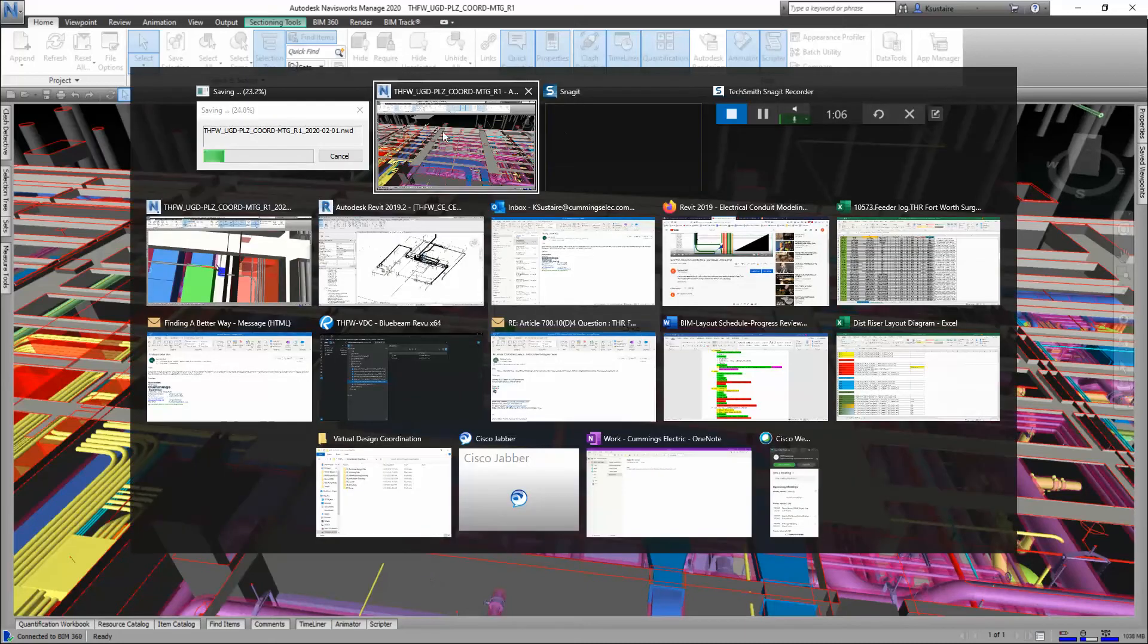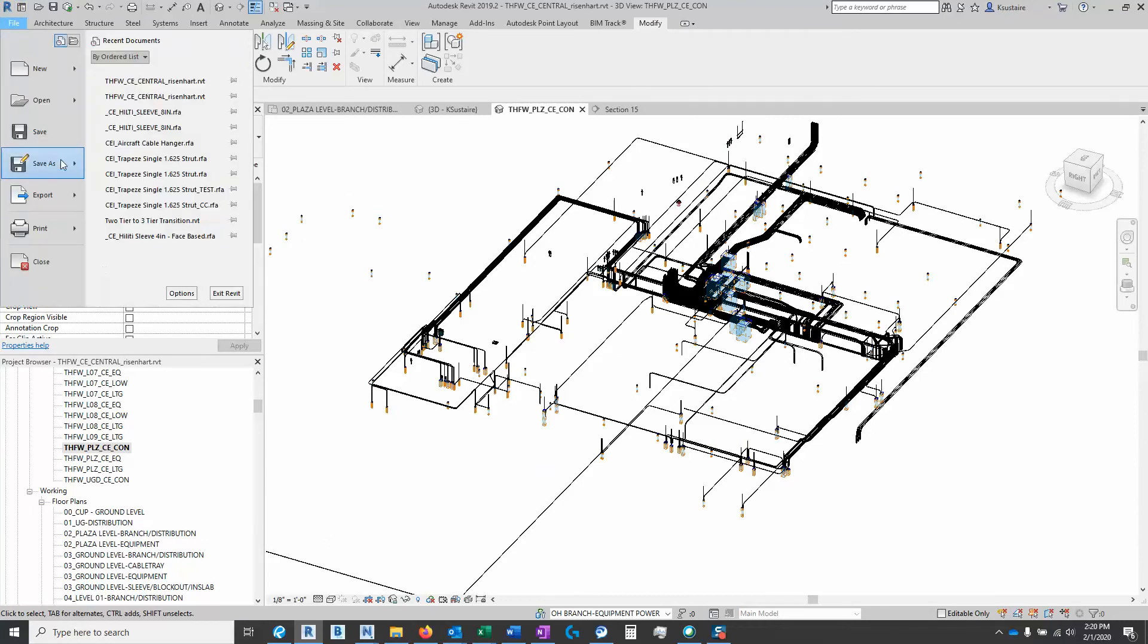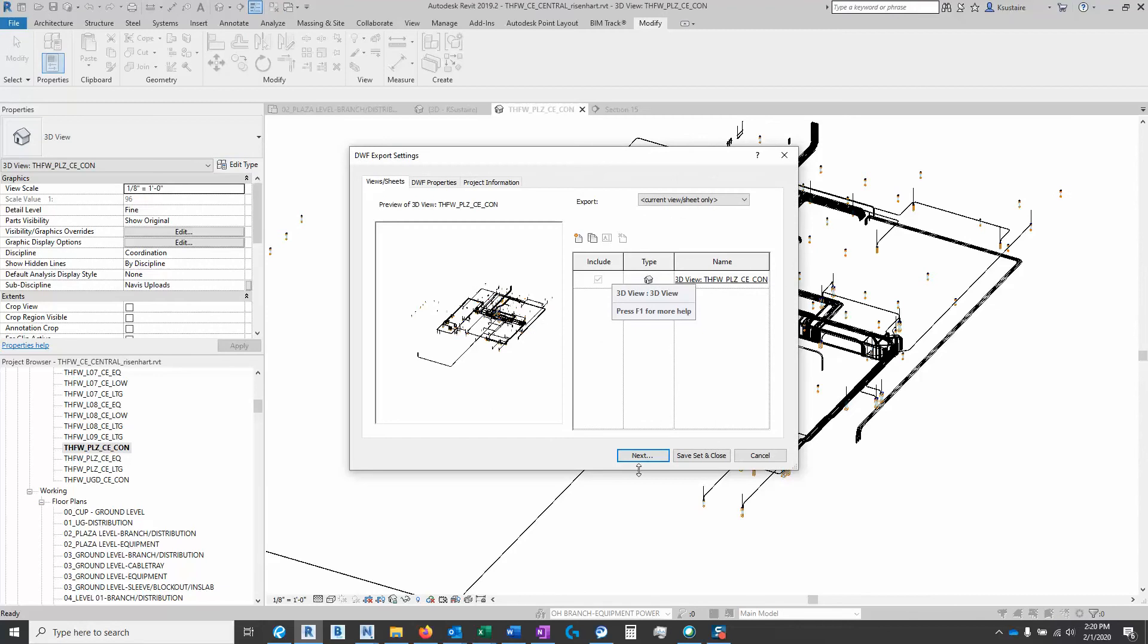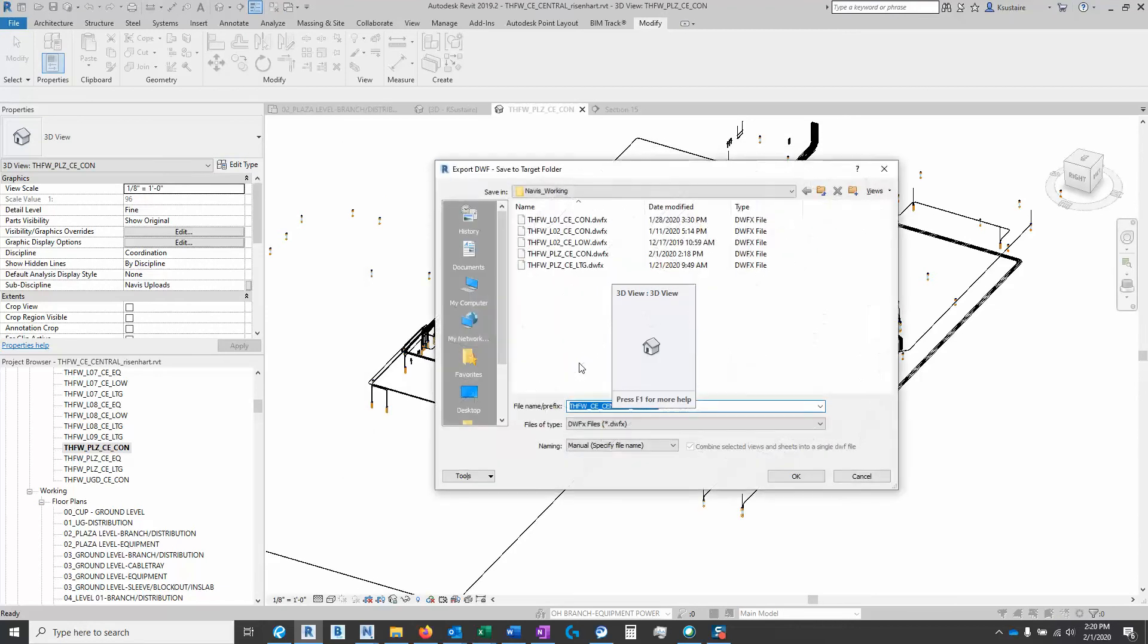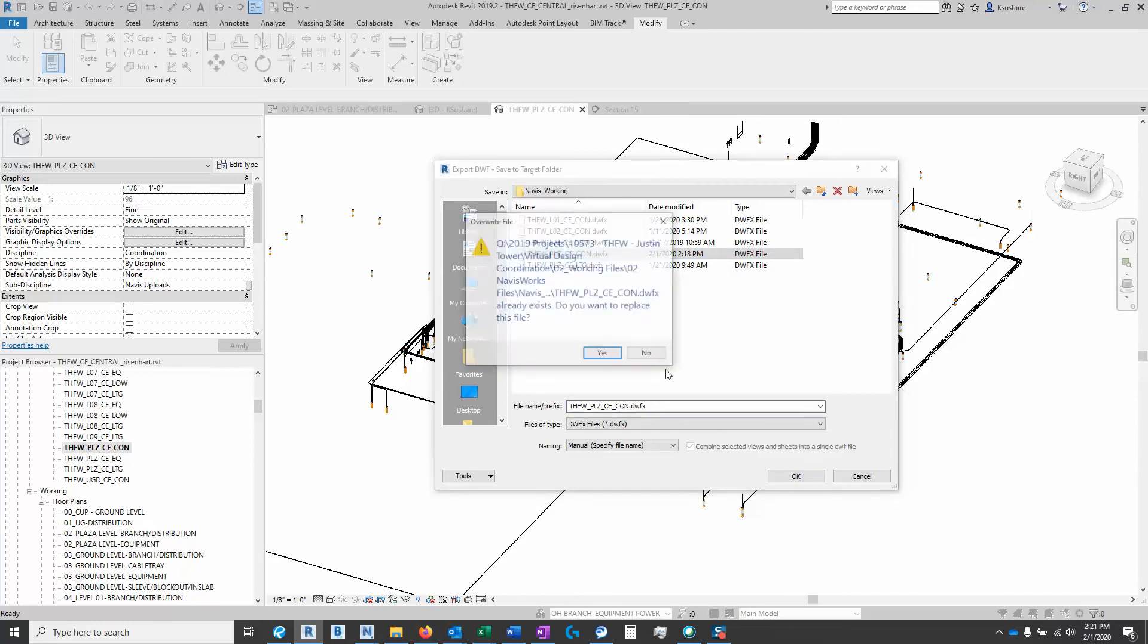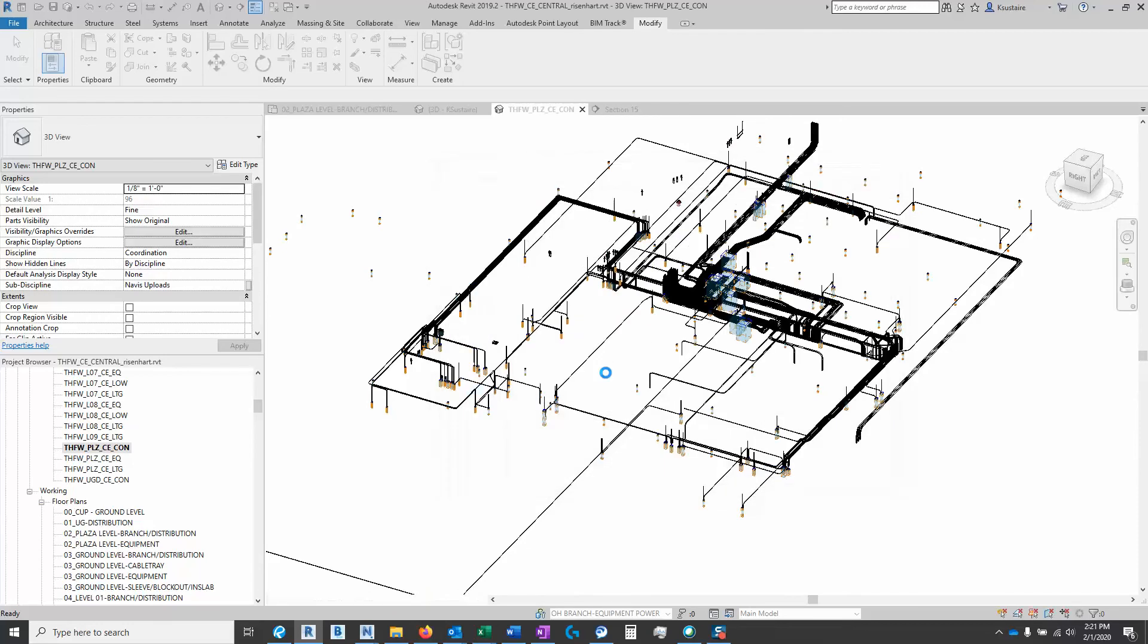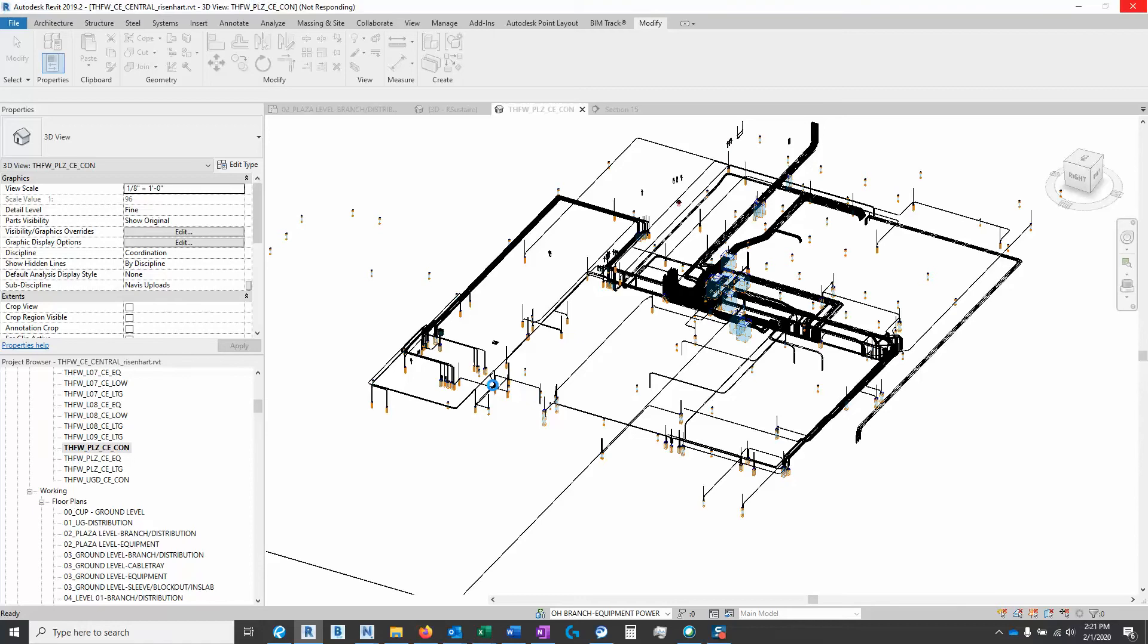And while that's saving, we're going to switch over to Revit and export a DWFX file. And the reason I save a DWFX versus, say, a DWG or NWC, there's a couple benefits. First, it'll export the colors. If anything's colored, it'll export it. DWG and NWC files don't export the colors. And this exports much quicker than a DWG or NWC.